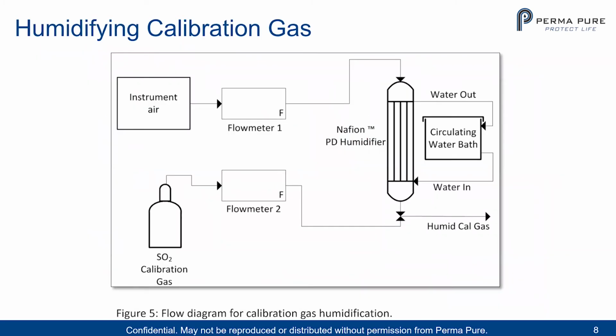Let's show here how we humidified our calibration gas. So we got the calibration gas with a certain level of SO2, and we needed to humidify it properly in order to make the measurements. And of course, we had to humidify the gas with one of our humidifiers using the same PD dryer. In order for us to do this, it had to be humidified in the vapor phase so we don't have any condensing water and lose the SO2.